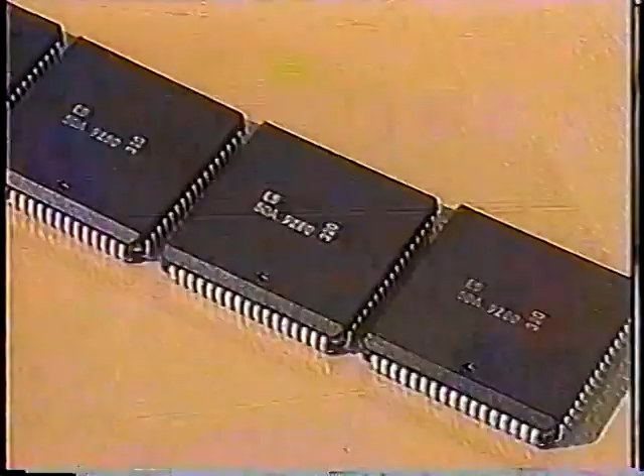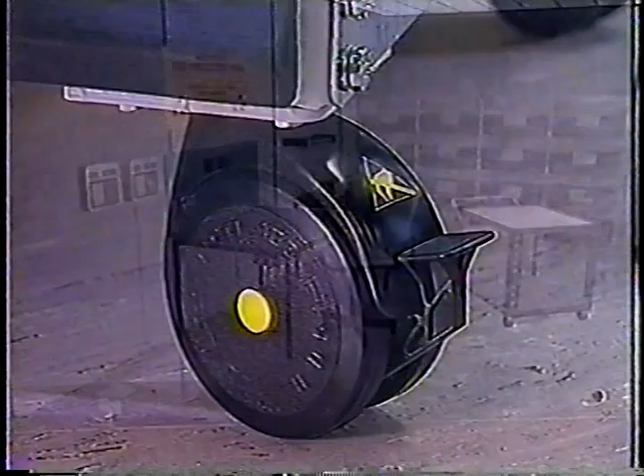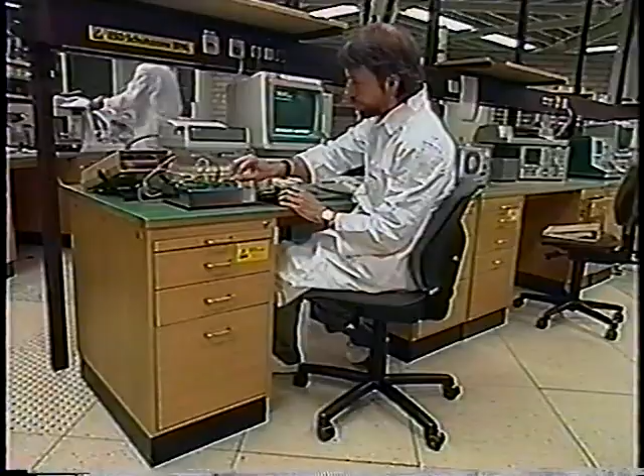Movable storage equipment is also fitted with groundable wheels. The same principle applies to chair wheels. The covers and upholstery are also made of dissipative materials. The use of highly chargeable insulative materials, especially in clean rooms, is often unavoidable for process reasons. They can be neutralized not by grounding, but rather only through the use of an ionizer. One highly sensitive area, for instance, is mask technology. Throughout the production of semiconductors, there are any number of procedures which might result in ESD damage, such as testing ICs while still in the wafer stage, bonding the connecting wires, trim and form, or checking the component with attachable electrodes.